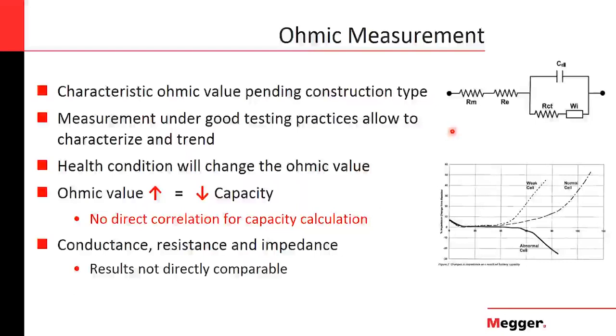And any change in the ohmic value is a direct indication of the change in the health condition of the cell. So that's why it's a test that is recommended in the standard and the 3 documents that we have for reference, and it's one of the main drivers to take any action on the batteries, because you can evaluate batteries very easily with this.